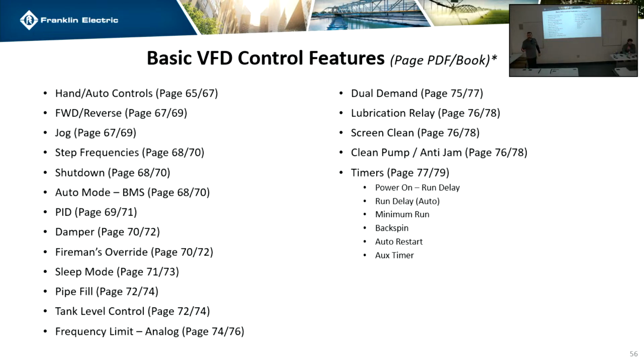And like we were just talking about, the drive itself is set up to go to sleep under the direct PID loop. So as the pressure is going up, the drive goes down. It says, oh, I've been operating at my minimum speed for 5 seconds. Obviously, I'm not needed. I go to sleep. For HVAC, because it's opposite, the drive does not understand that it needs to go to sleep at full speed or at a full signal. So we have to incorporate the output relay to look at the analog signal. And if it drops below a certain level, the drive will go to sleep. And if it comes back up, it'll wake up. So it's still automatic. It's just a tiny bit more programming.